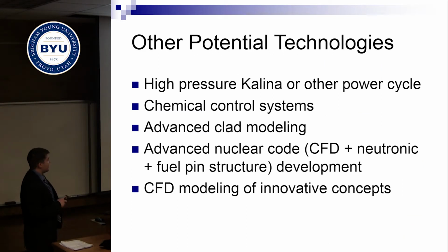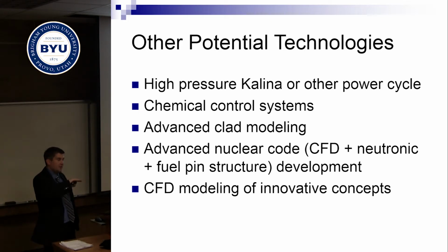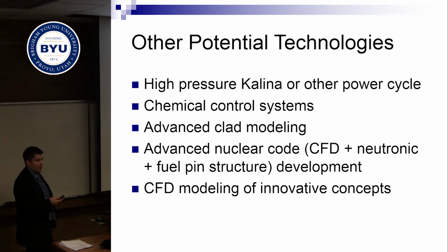There's other potential cycles—I mentioned the cost cutting. There's a lot of interest in the Kalina cycle, that's a water-ammonia mix instead of just water. What happens is it's not isothermal when it boils, so it actually increases in temperature, which allows for higher efficiency. And 1 point of efficiency, if I remember right, equates to a couple million dollars a year in revenue for these plants, so getting more efficiency is a very big deal.